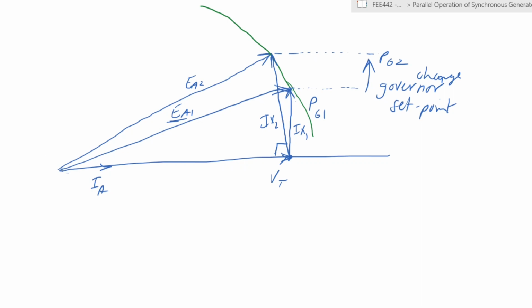And that means that, consequently, your current here as well will change, IA2. Your current will change to match the change in those. So what this means is, if you change the governor set point, if you want to supply more active power, but you don't want to change the excitation, the power factor of the generator will change. You will now have a more leading power factor. And if you increase the power even further, your current will move more towards that direction. It will be more leading, and you will have more of the power factor change.